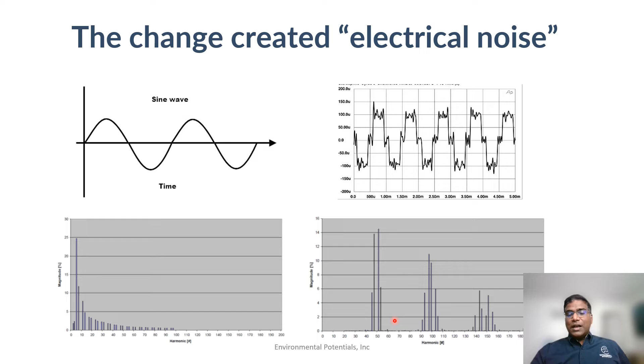The other thing we see in a facility are lightning strikes and power grid failure, which is pretty common in the Philippines market at this moment. Here's an interesting factor. Everybody thinks that the surges, the external noise, the transients always come from lightning strikes and the power grid failure. But in reality, they constitute only about 15% of the total surges. This is coming from a huge data set they did in the United States. 15% of the surges come from outside, whereas 85% of the surges and noise come actually from within the building, which means basically from the nonlinear loads.